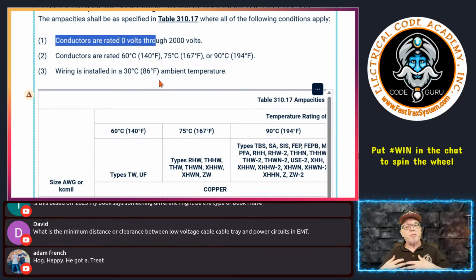You're just given permission because these conductors are going into a cable tray, and it assumes you're installing them under the guidance of 392.22(B), which has all these rules for how you can put these conductors in there. Once that's done, it's saying, because it's open at the top, it's typically going to allow heat to dissipate better and circulate, so we're going to let you use a little higher ampacity. And that's what you get down here.